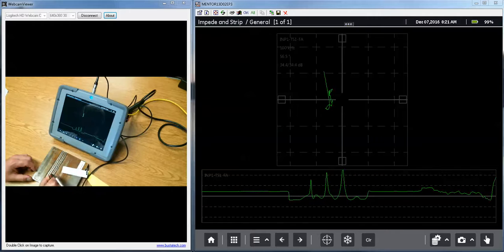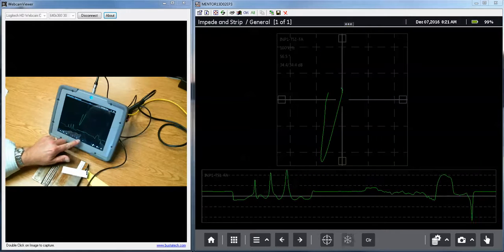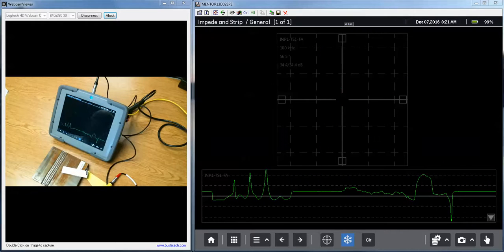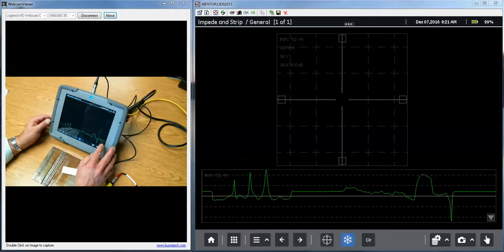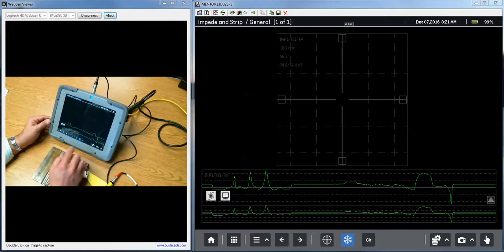If I run along the weld, I see an indication. I pause. I have my strip chart set up to record the last ten seconds of things that I've done.